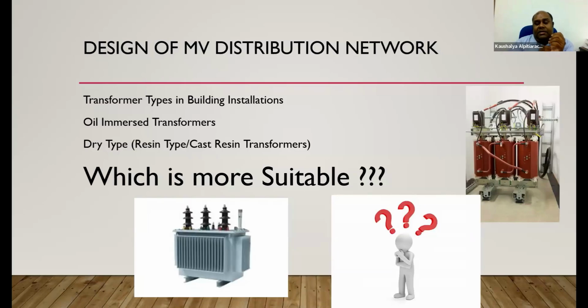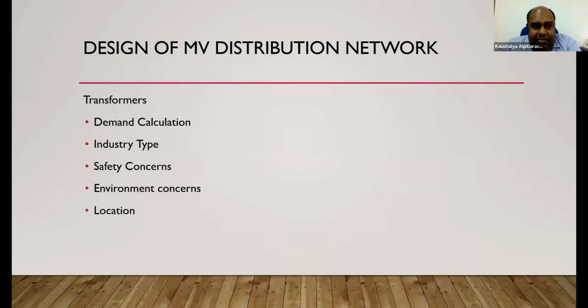Design of medium voltage systems, transformers. Transformer types in buildings: oil immersed transformers, we see dry type, resin type, cast resin transformers. Which is more suitable? Can we come to a conclusion? Yes, before that, it needs the following inputs: demand calculation, industry type, safety concerns, environment concerns, and location. If it's an outdoor installation, you can have an oil immersed transformer. If the industry has more harmonics, or that is referred to develop more heat at the transformer level, that means your dry type transformer is not going to work there.